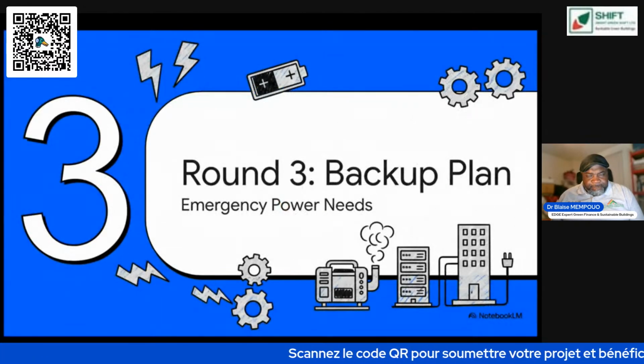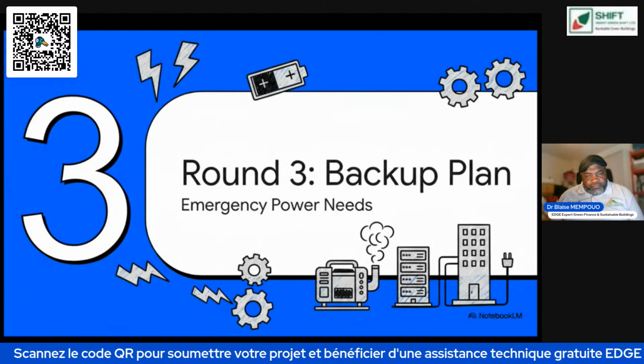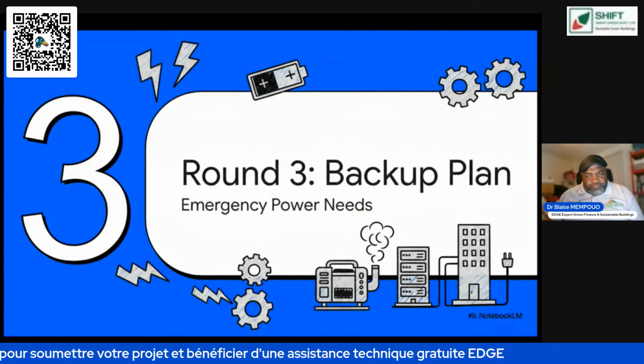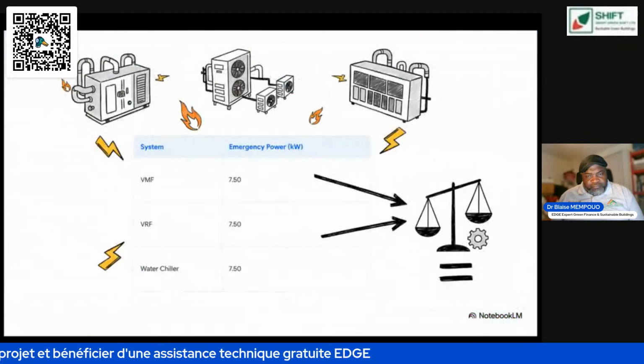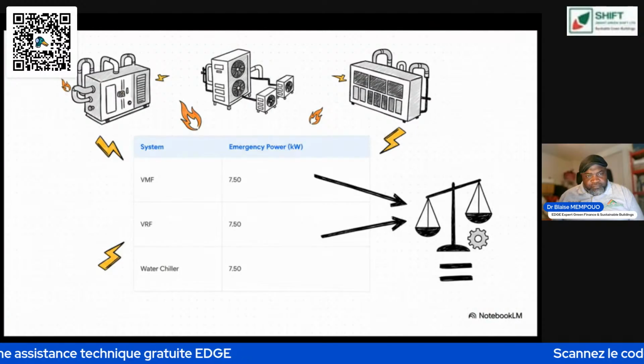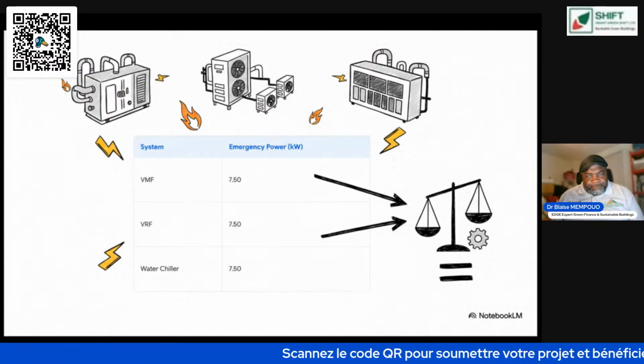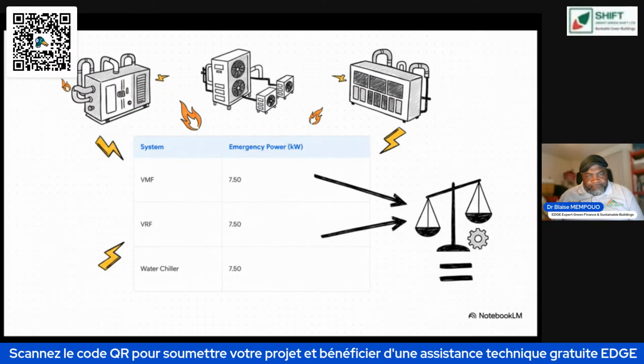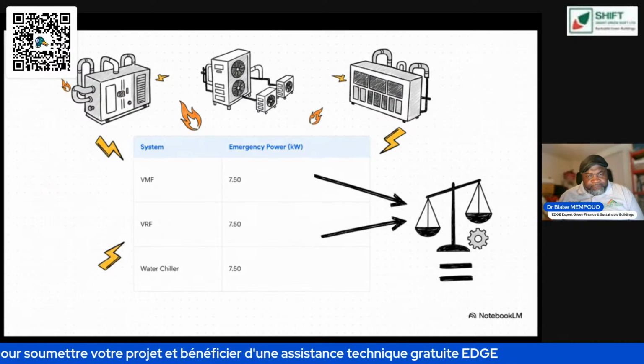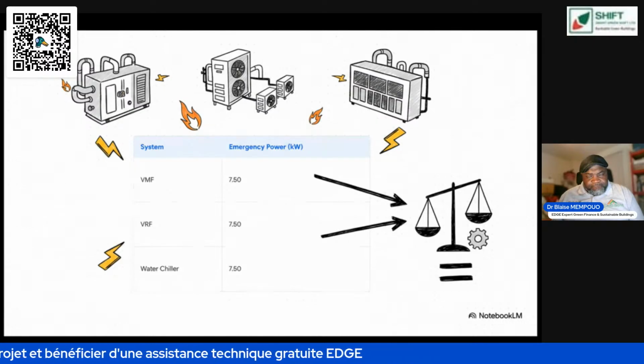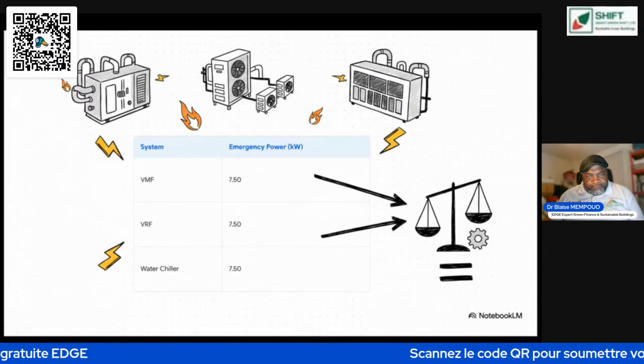Let's move on to our final round, the backup plan. What happens when things go sideways? We need to look at the emergency power needed to keep essential functions running. After such crazy differences in every other category, you won't believe this result: it's a perfect tie. All three systems, the VMF, the VRF, and the water chiller, require exactly 7.5 kilowatts of additional power for their emergency heaters. It's this fascinating moment of total equality in what's been a battle of extremes. It just goes to show that some operational needs are universal, no matter how the system is designed.